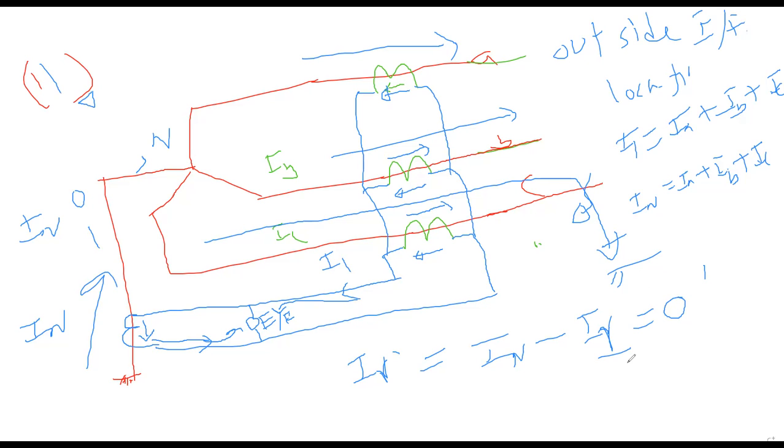How come it operates? Is the fault inside the zone or outside the zone? When we get a zero result, sir. If your relay coil has a resultant current of zero, the relay should not operate, right? Yes, sir. Okay. Now we are considering restricted earth fault protection, isn't it? What we have done here is placed a restriction, right? Within this zone, if an earth fault occurs, the relay should operate, and outside of this zone, if an earth fault occurs, this relay should not operate. That will be handled by some other device. We do not have any problem.